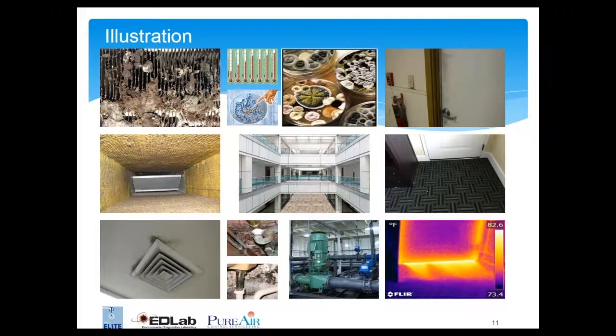This is one more thing I want to focus on. If you do thermographic imaging on this particular picture, you can see that it tells a lot of a story, like whether there is a water leak and so on. This is a recent technology by which we can non-invasively find out if there is a problem, because if there is moisture and temperature, then you are vulnerable to getting mold. So that's one of the things.